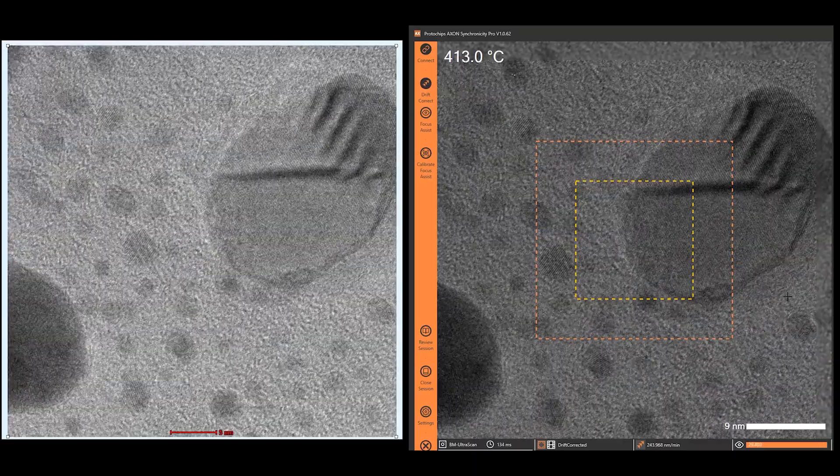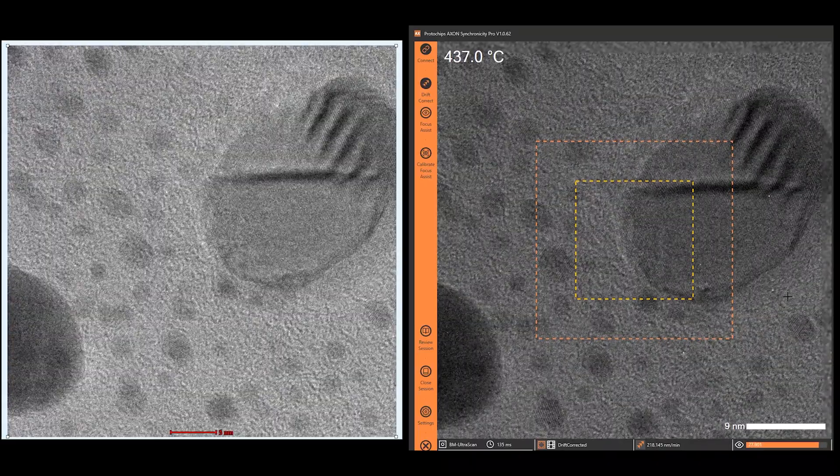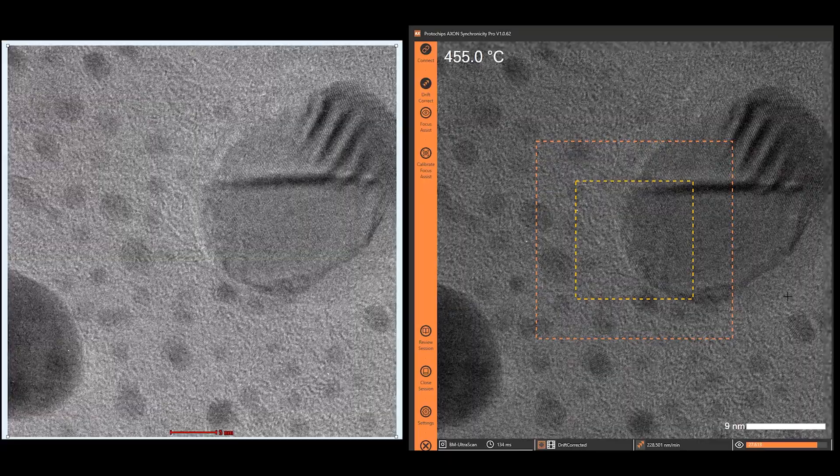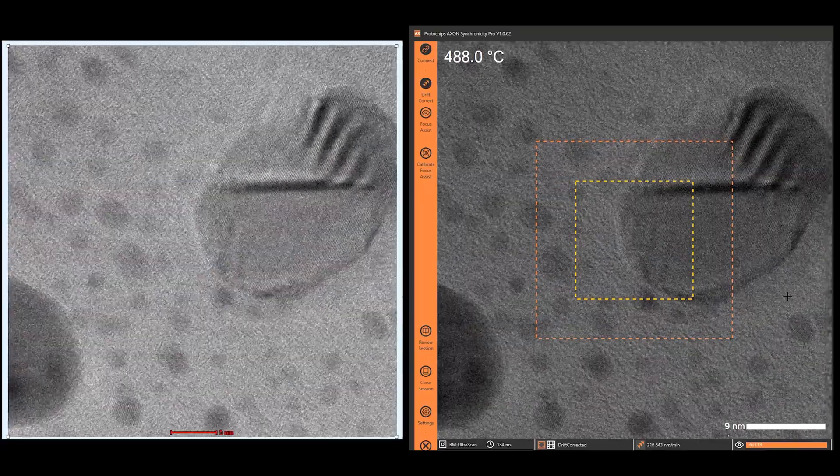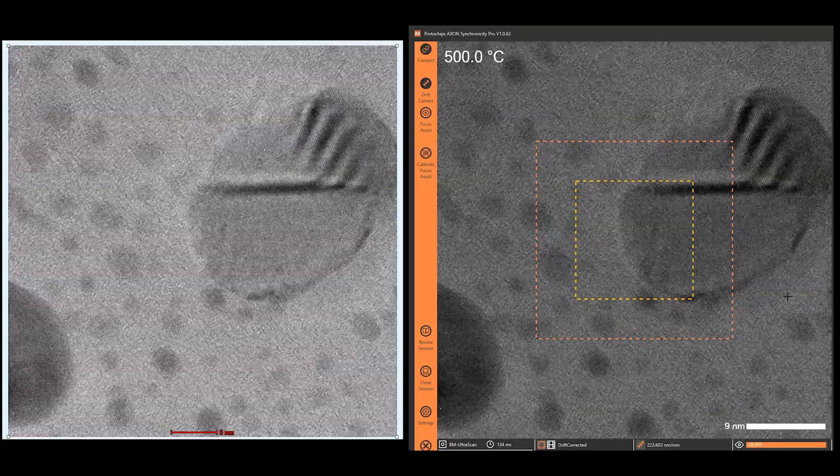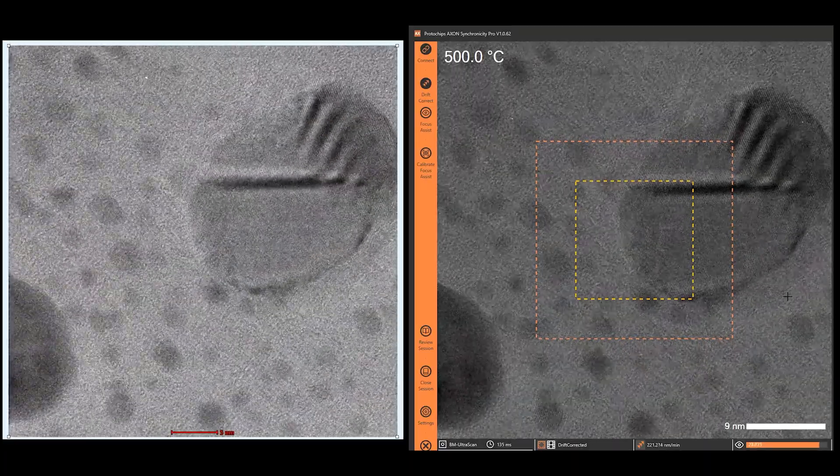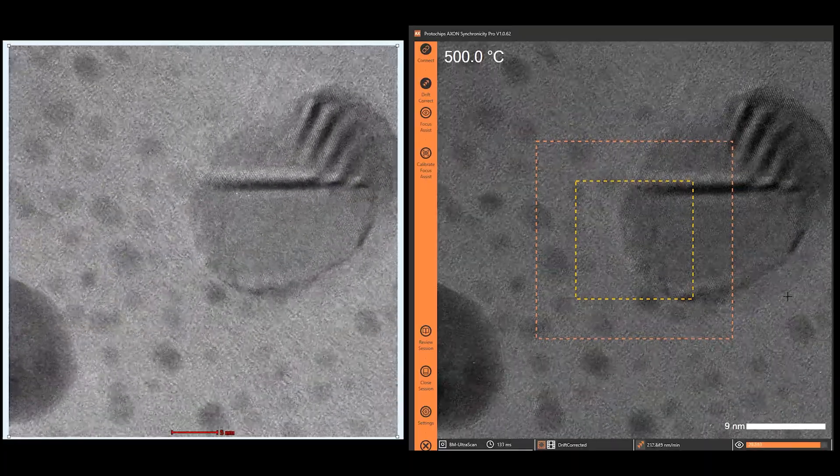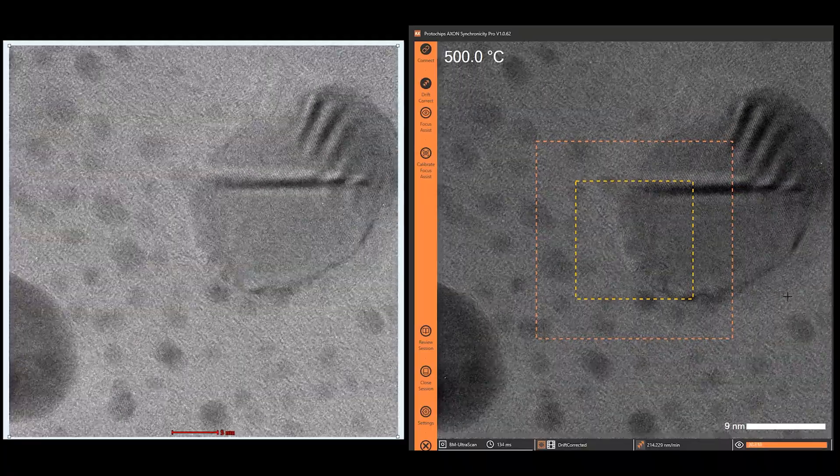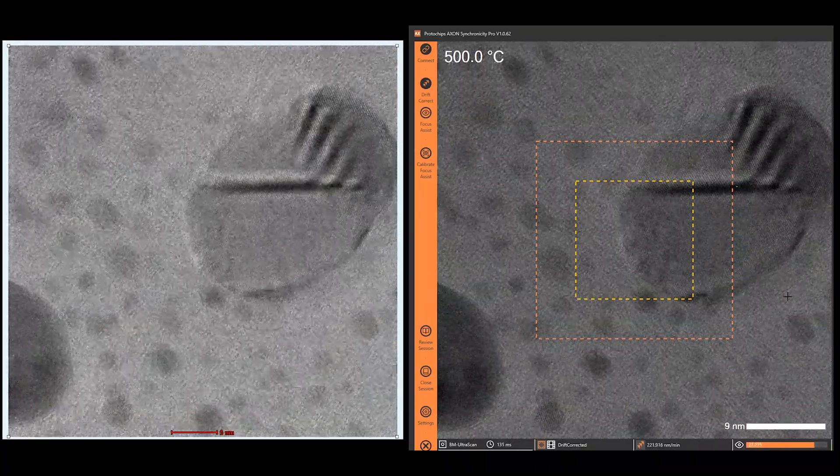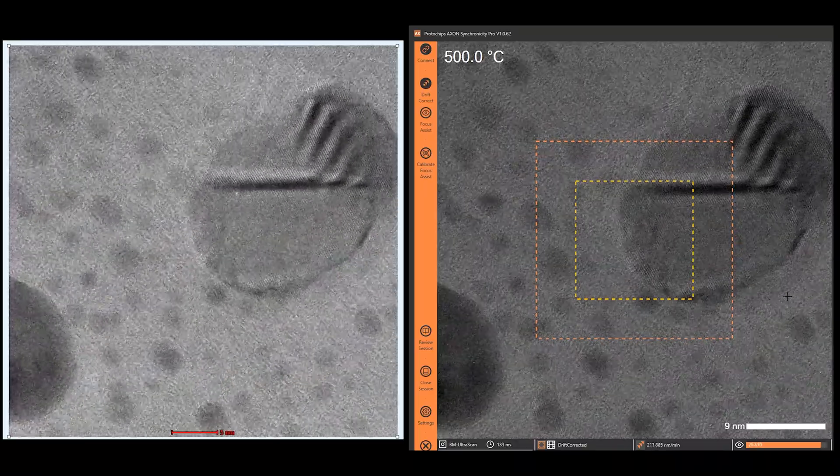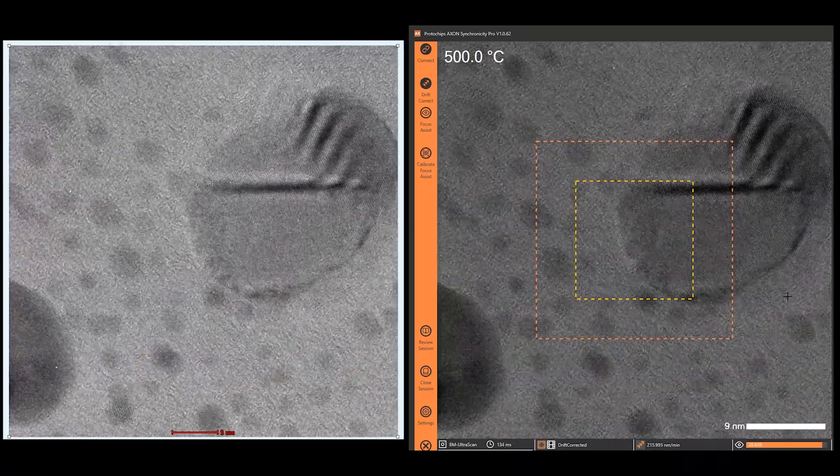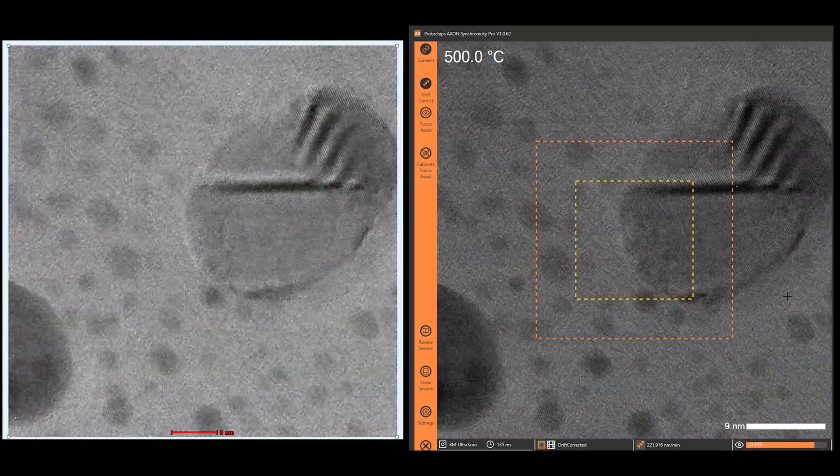Looking at the TEM screen on the left shows the raw truth that the image continues to drift rapidly at more than 200 nanometers per minute as reported on the Axon status bar. The jumping you see is Axon adjusting the sample position and resetting the alignment of the beam over and over to maintain perfect placement of the image being collected. Axon will automatically utilize whichever column adjustments it needs from the coarsest mechanical goniometer movement to the finest beam shift.